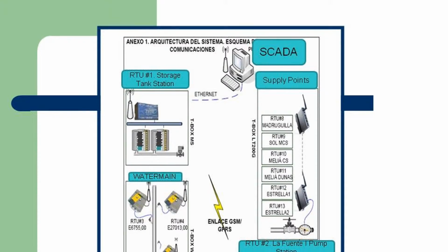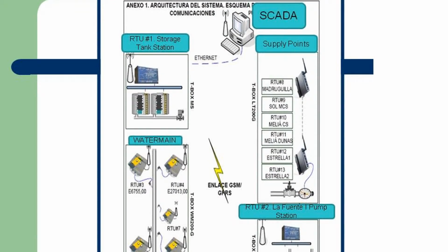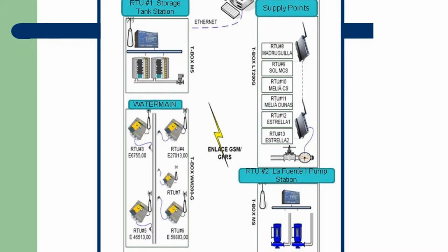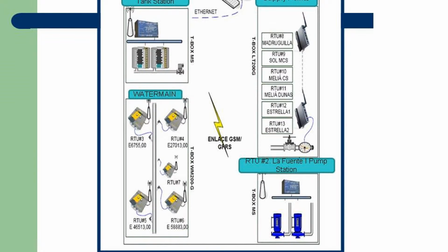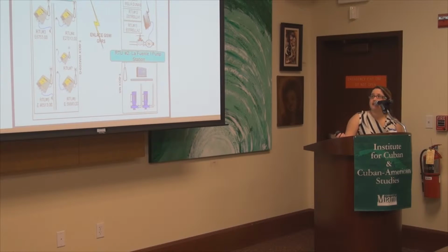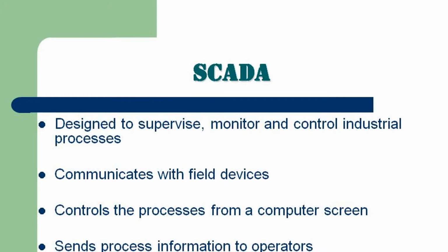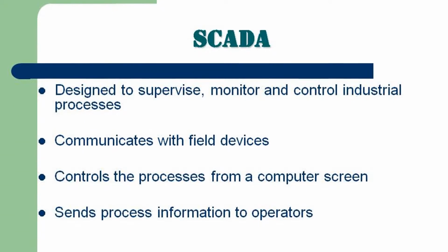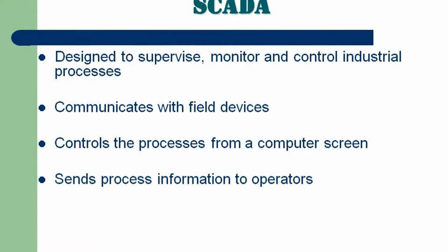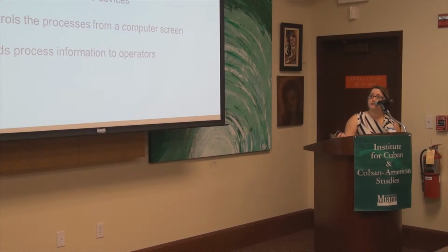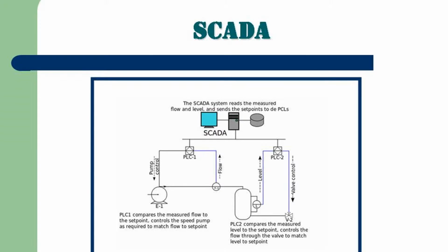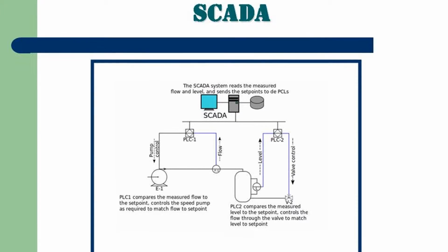This is a diagram of the communications. You're going to have a SCADA system, which is going to provide visual control of the overall system. You're going to have 13 RTUs installed throughout: 1 at the tank station, 5 along the water main to measure pressure, 6 at the distribution points, which are the hotels, and 1 at the pump station. So what's SCADA? SCADA is designed to supervise, monitor, and control industrial processes. It communicates with field devices. It controls the process from a computer screen, and it sends information to the operator. And this is a diagram of how SCADA communicates with the different field devices.